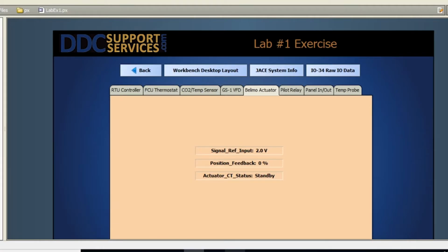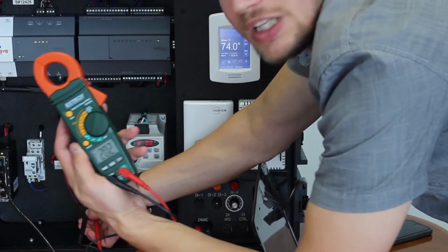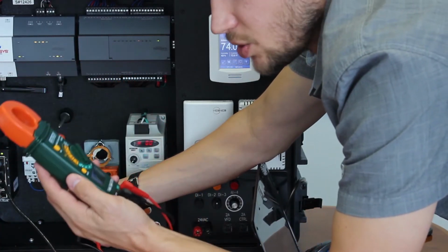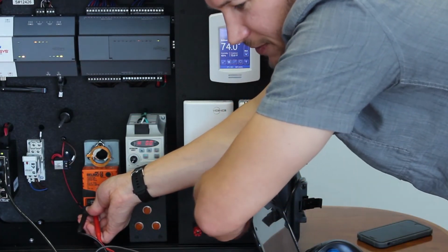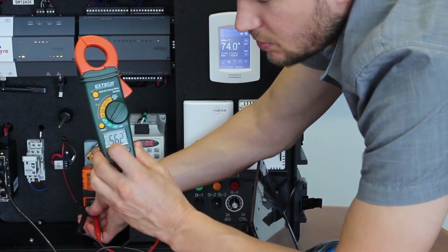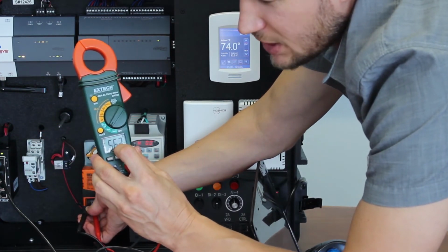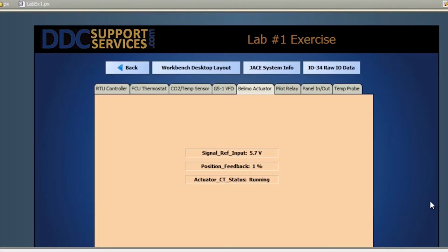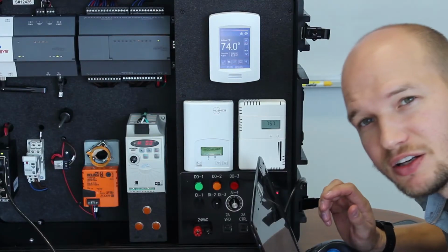On the computer here, we can see signal reference input 2 volt, position feedback 0%. You can see that we're at 2.02 volts. Now if we bring this up to 50%, you see that climb to 5.62, and on the computer screen we got 5.7. You can see the position feedback starting to rise up, and eventually that'll get to 50%.